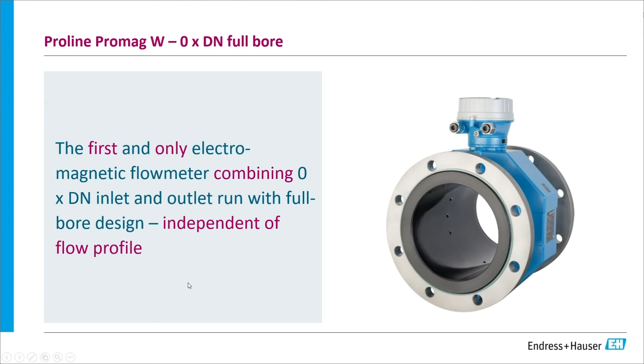By adding additional electrodes and enhancing our transmitter technology, we can now do this with a full bore meter design. So there are no limitations on the installation or performance of the meter. We can now install our mag meters directly after 90-degree bends, open valves, things like that with no impact on meter accuracy. Click on the next slide.